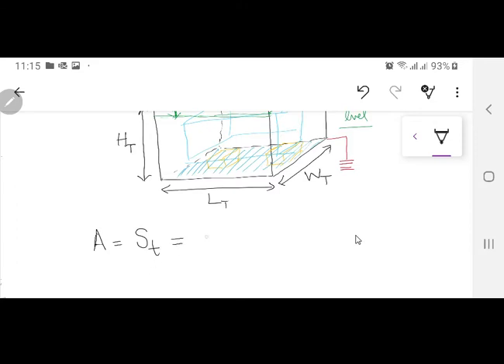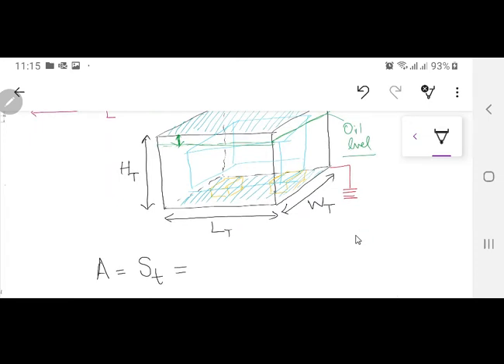Now A or ST is the effective surface area. This will accommodate only the sides. Let me show you how to calculate the surface area here. We have dimensions LT, WT, HT: 2 times HT multiplied by WT, plus 2 times HT multiplied by LT. These are the four sides. So the effective surface area by which you are dissipating the heat is ST, surface area of the transformer.